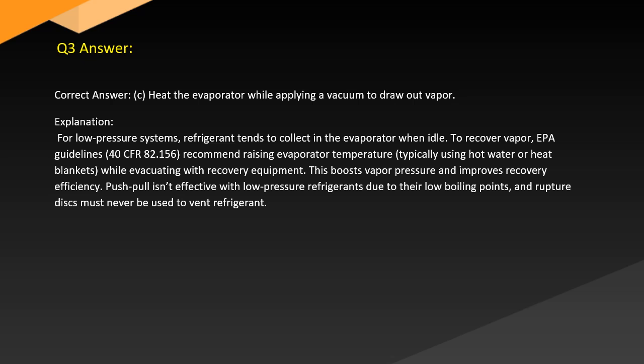Answer. Correct answer: C. Heat the evaporator while applying a vacuum to draw out vapor. Explanation. For low-pressure systems, refrigerant tends to collect in the evaporator when idle. To recover vapor, EPA guidelines in 40 CFR 82.156 recommend raising evaporator temperature, typically using hot water or heat blankets, while evacuating with recovery equipment. This boosts vapor pressure and improves recovery efficiency. Push-pull isn't effective with low-pressure refrigerants due to their low boiling points, and rupture discs must never be used to vent refrigerant.